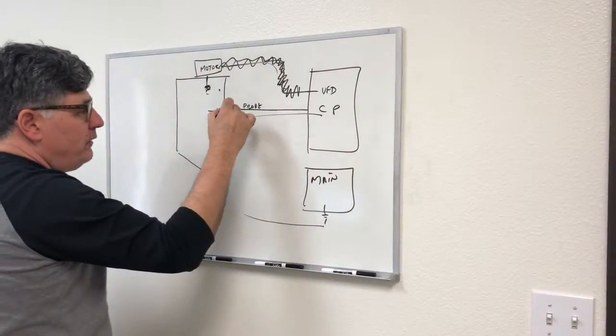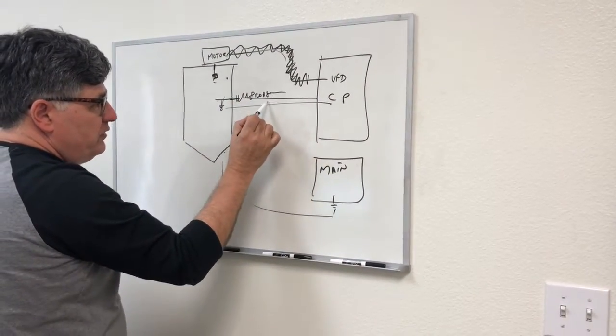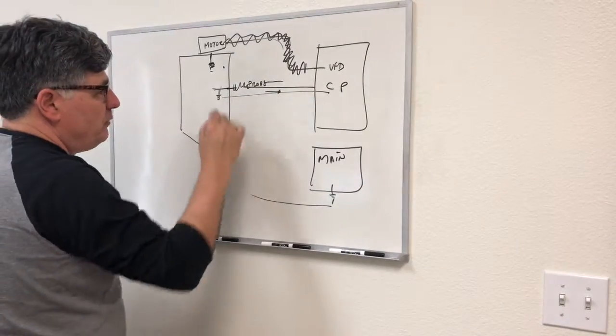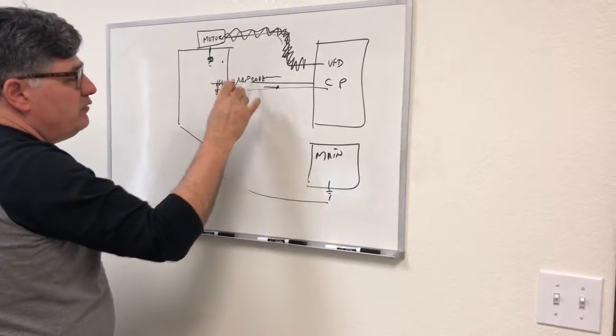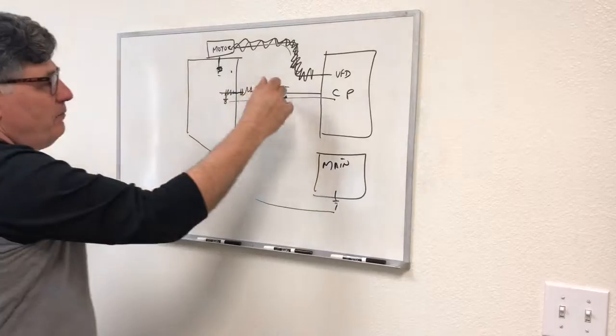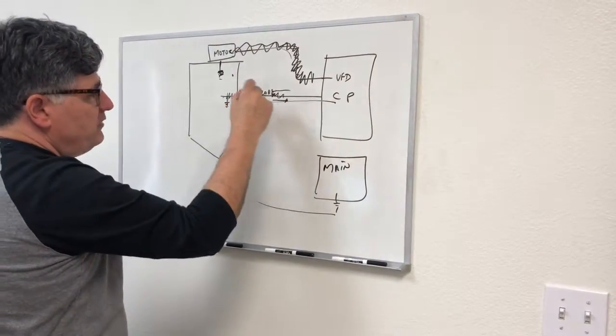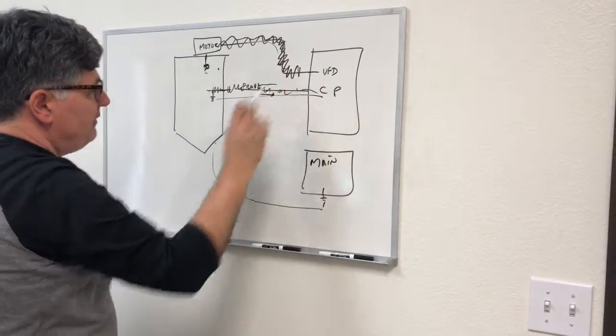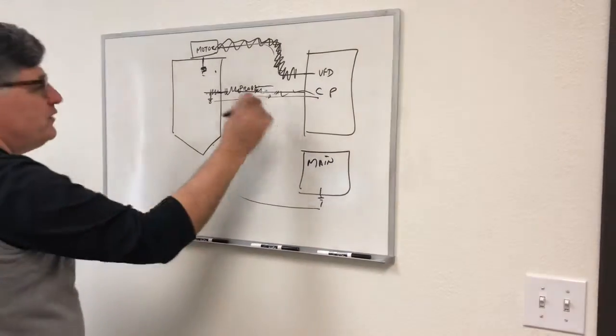adding a little bit of interference, because this puts out a voltage, and the voltage has to come back from this temperature probe, and this little interference just kind of slightly messes up the signal wire. It starts to fluctuate back and forth here, back to the control panel. That's what you're seeing, and that's why you're seeing a fluctuation.